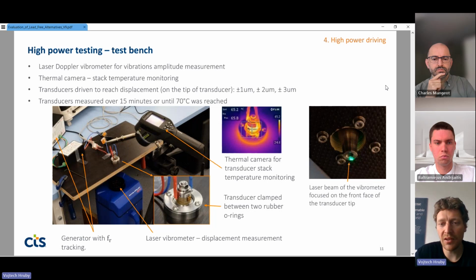So we prepared three driving scenarios. The first one was ±1 micrometer displacement. The second one was ±2 micrometers displacement. And the third one, ±3 micrometers displacement at the transducer tip. We drove transducers over 15 minutes, or until the temperature of the transducer stack reached 70 degrees Celsius. As you see, the transducer was clamped using 2 O-rings inside the fixture.